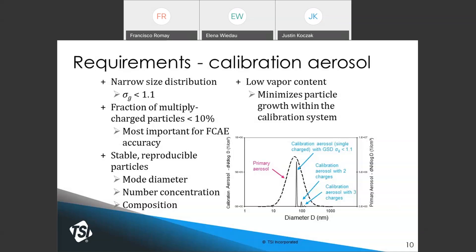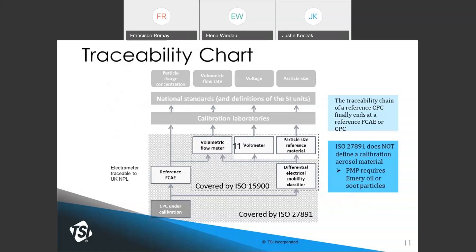The aerosol needs to be highly reproducible and stable with known particle composition and low vapor content. For traceability, measurements must trace back to national standard SI units. Most importantly, the reference electrometer or reference CPC must be traceable — in TSI's case to the UK National Laboratory, NPL. The flow meter also needs to be traceable, in TSI's case to NIST.